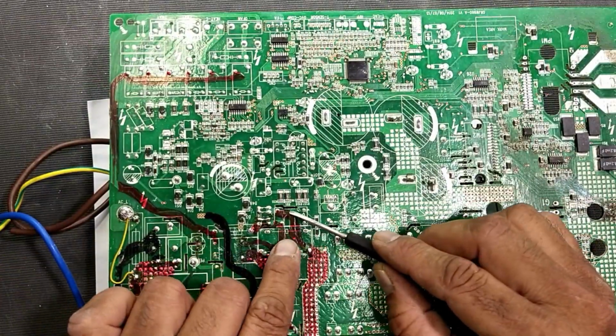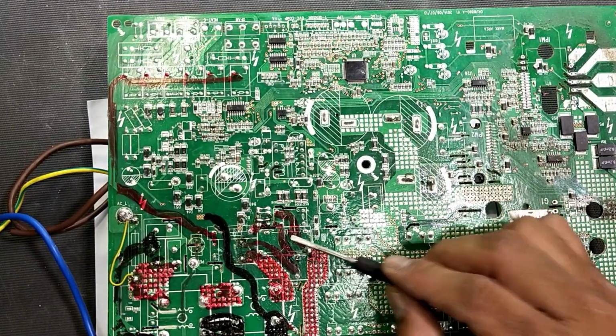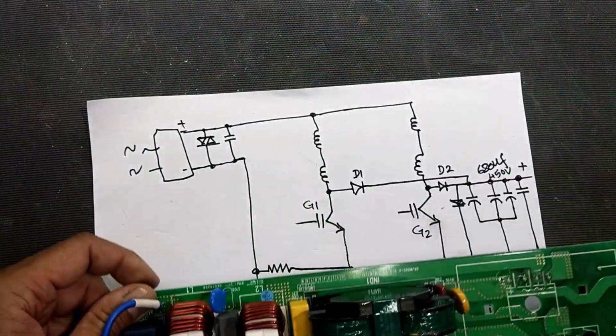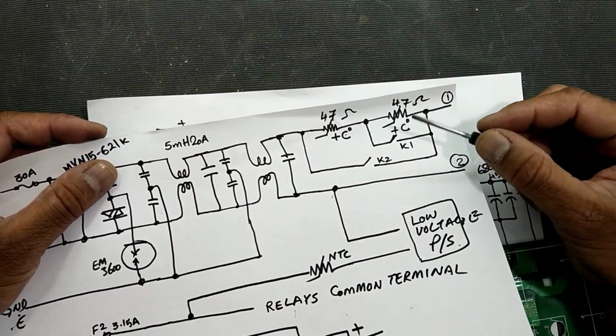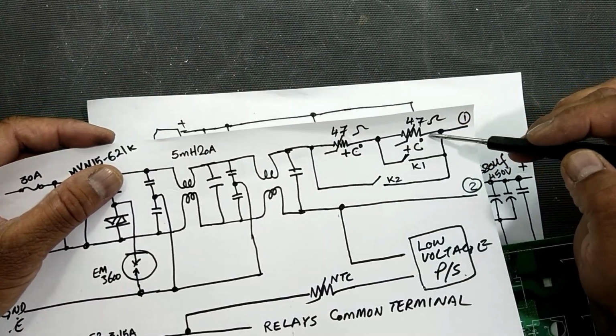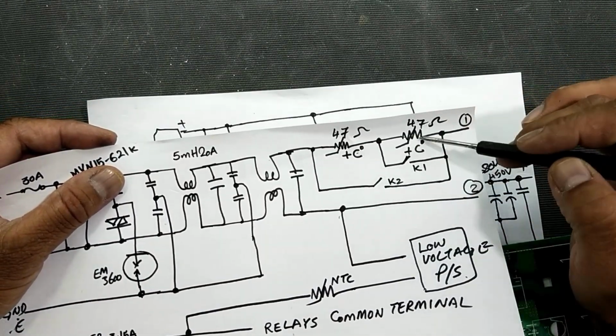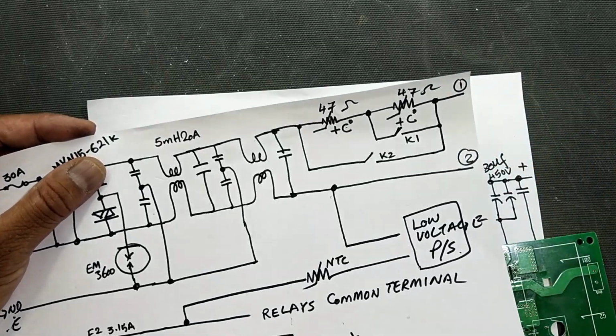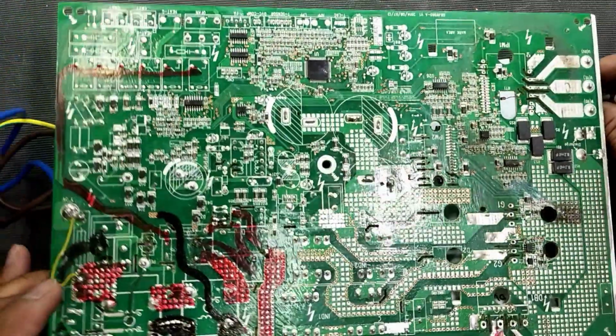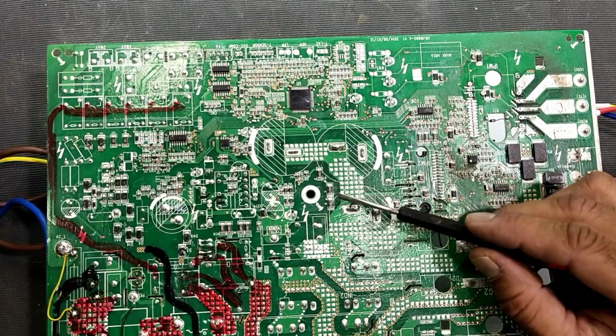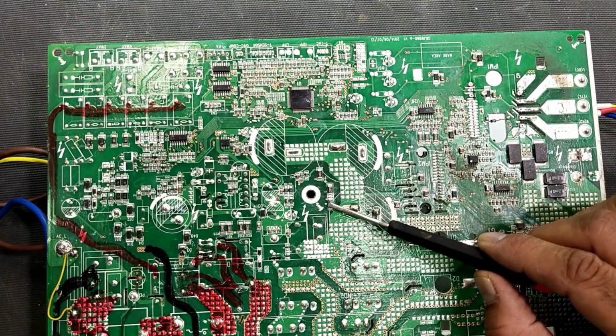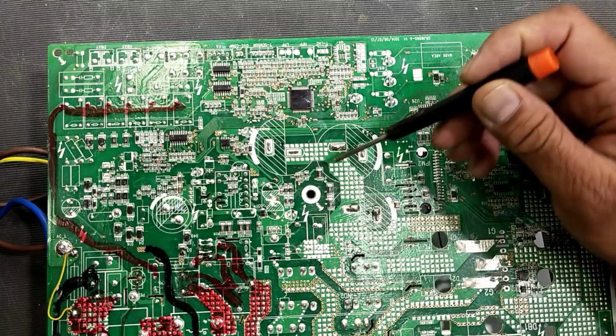In that case it will drive these bypass relays, K1 and K2, to bypass these and the PTCs, positive temperature coefficient resistors. So if it gives a high or low voltage error, we have to check this section.